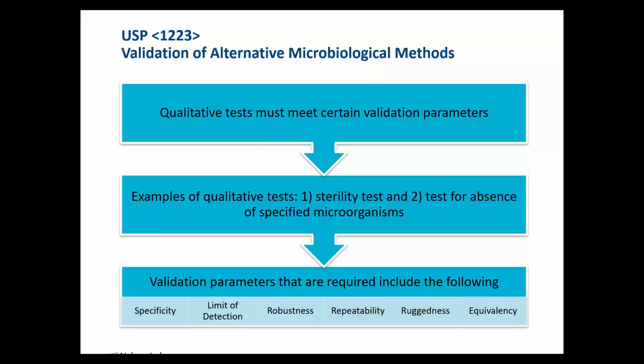First thing is that the test is considered to be a qualitative test. So there are certain validation parameters that need to be achieved in order to validate this alternative approach when it's a qualitative test. Some examples of a qualitative test would be the sterility test and a test for absence of specified microorganisms. And certainly BI testing falls into that category. It's commonly referred to as a BI sterility test, and we are definitely looking for the presence or absence of a specific organism. In this case, we'll be talking about Bacillus atrophaeus.